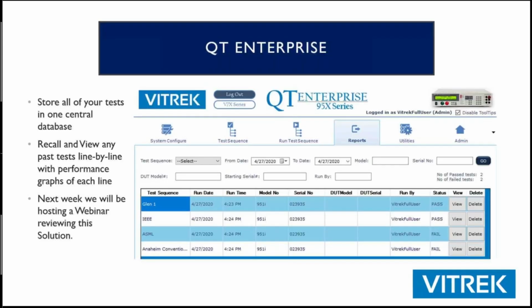So to take it one step further, we recommend using software and a database to store all these records. If you choose to use our QuickTest Enterprise software, you're going to have the ability to have a log of every serial number that you've tested. This can be entered manually or with a barcode scanner. Date, time, the user. You can see what the test limits were and whether it passed or failed. Eventually, you're going to be able to build an entire database, and you could use it for analysis. You could look back and say, does this operator have more failures? Are they running more products through this line versus that line? And it's really a very useful tool for a manufacturer.